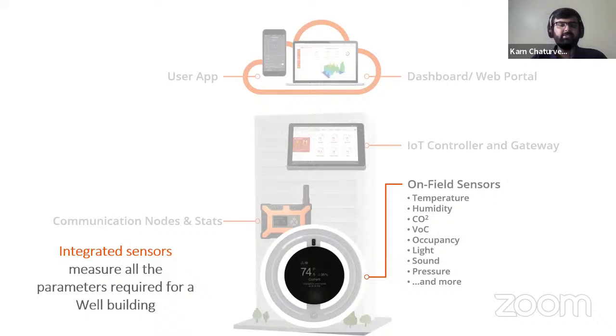So it's very important that this data is accurate and usable, at a certain frequency. If we're able to have these sensors integrated, that would be even better. Sensor data should not be restricted to temperature or humidity, but other factors impacting occupants too - CO2 levels, VOC levels, both shown to have high correlation with occupant performance, light levels, and occupancy levels. If collected through integrated sensors, that makes it very easy. At the same time, these sensors should be quite accurate and maintain their accuracy over a longer period of time. Ideally, if they have auto-calibration sequences, that would be very useful, so we can be sure the data coming in from all these sensors is reliable.